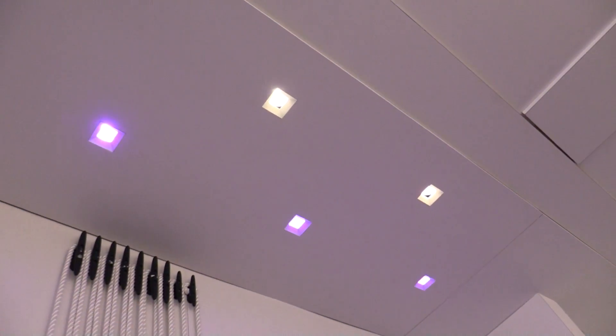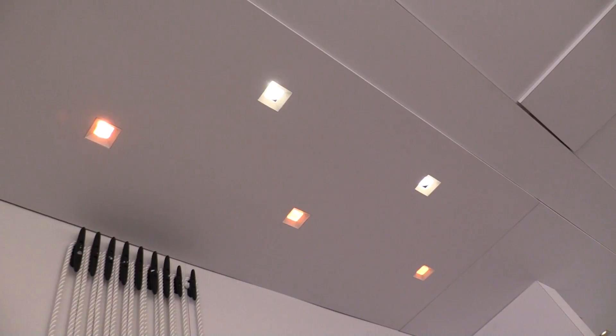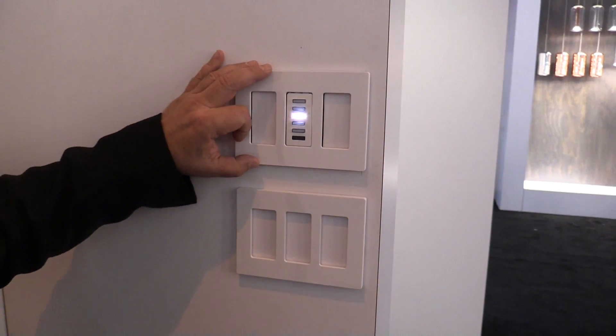The Luminetics Programmable White allows a range of white light selection and the ability to adjust saturation and hue. Dimming is via two sets of 0 to 10 volt lines, and commissioning options are DMX and Bluetooth. Scenes can be preset.